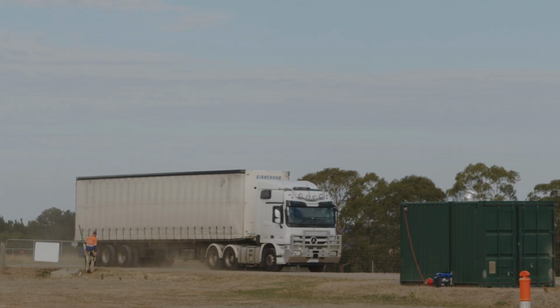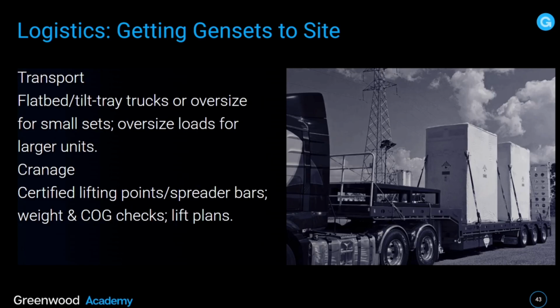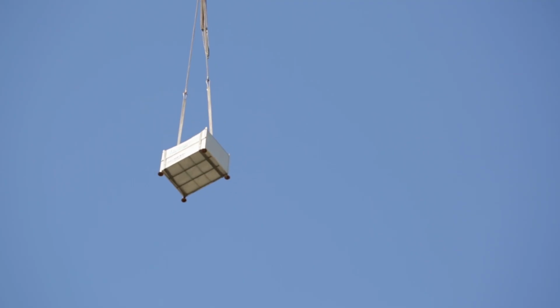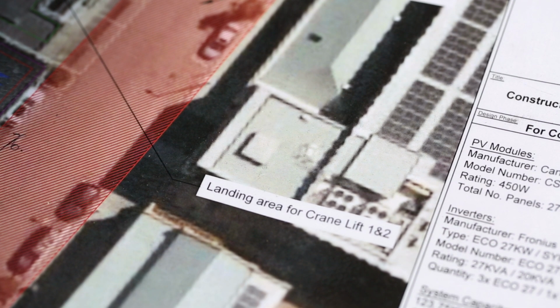Logistics, getting gensets to site. Flatbed tilt trays or trucks for small sets, and oversized loads for really large units. In some instances, you're using a crane, so you'll have to look at certified lifting points, spreader bars, weight, and COG checks and lift plans, which is very important.